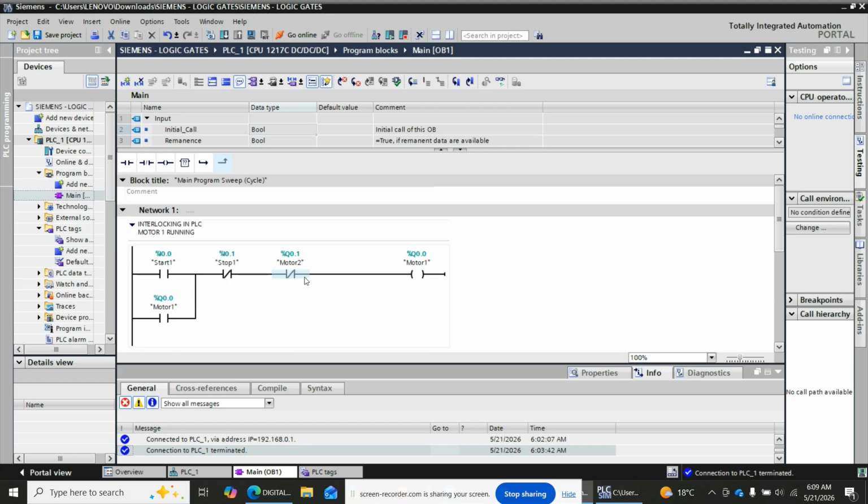Manake sasa nikiwa if the motor is moving forward, unless you stop it, you cannot press the reverse button and it responds. So if the motor is going forward, it will keep moving forward. If you want to take it in reverse, you have to press the stop button first, and then you press the reverse, then it goes reverse. Okay? All right. So let me compile this.